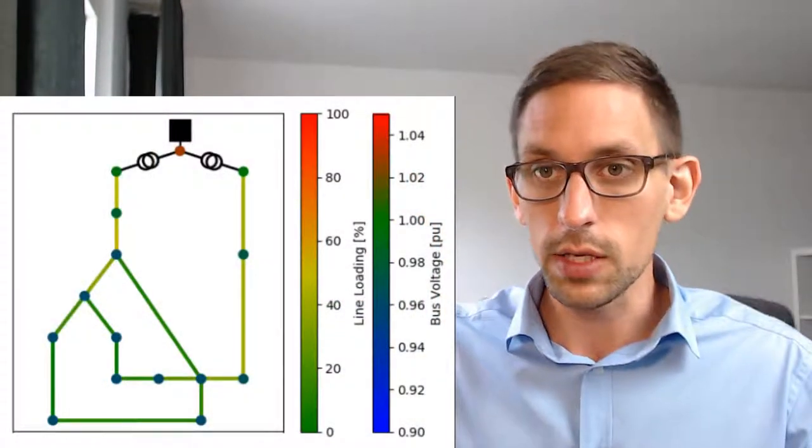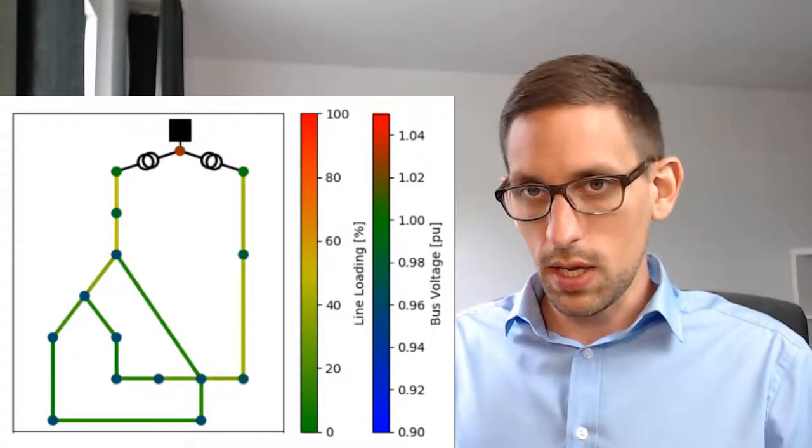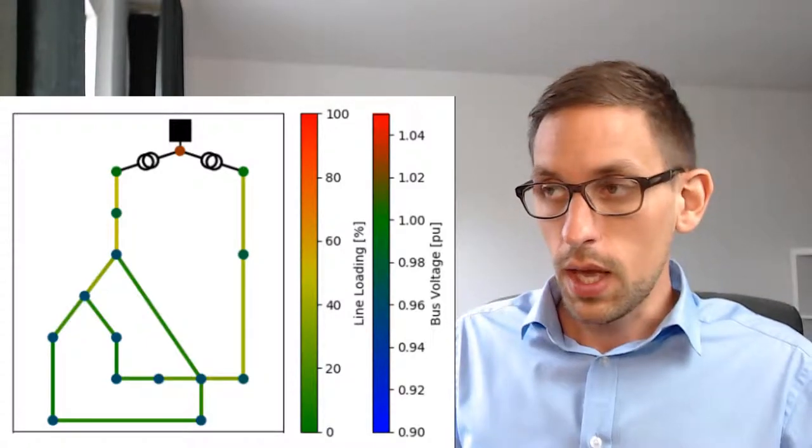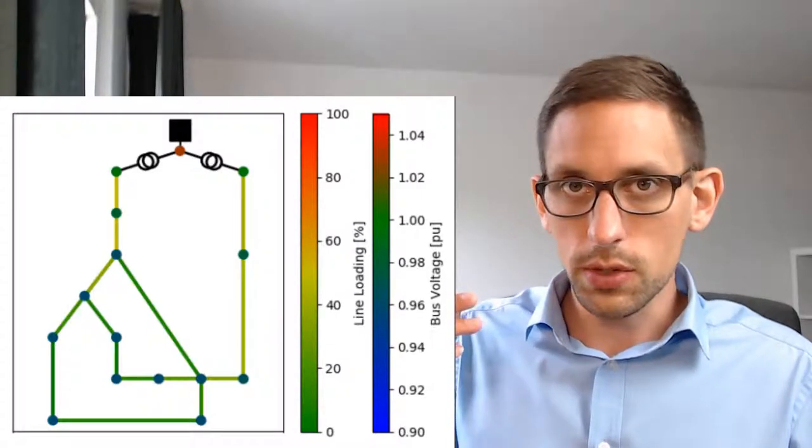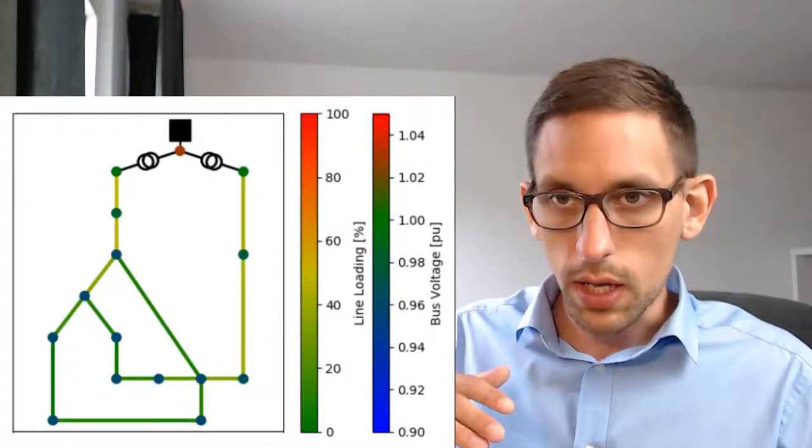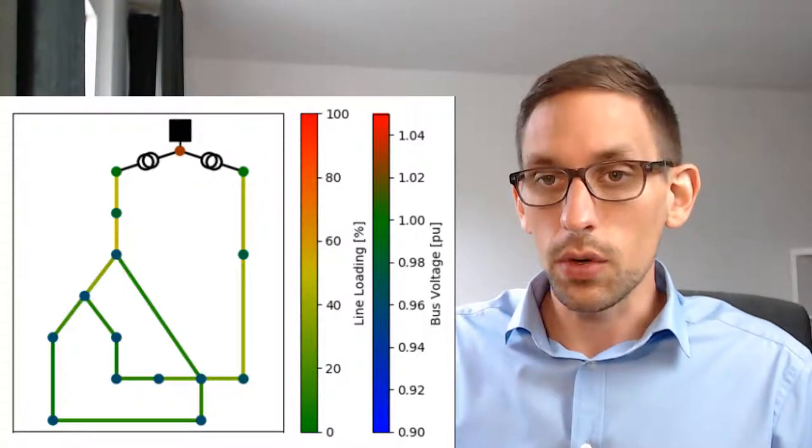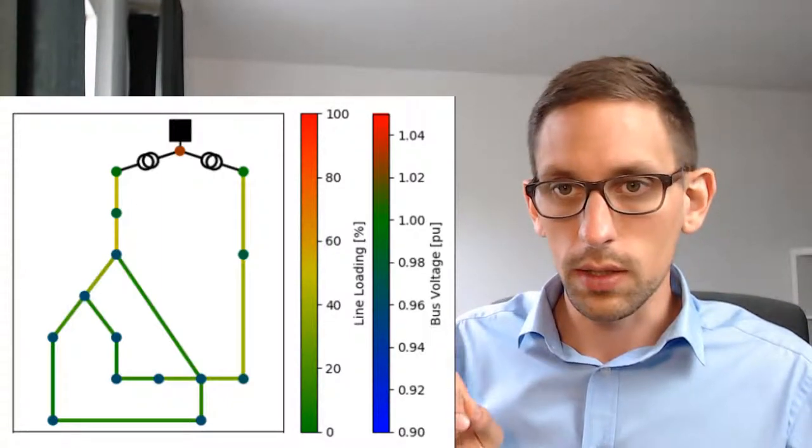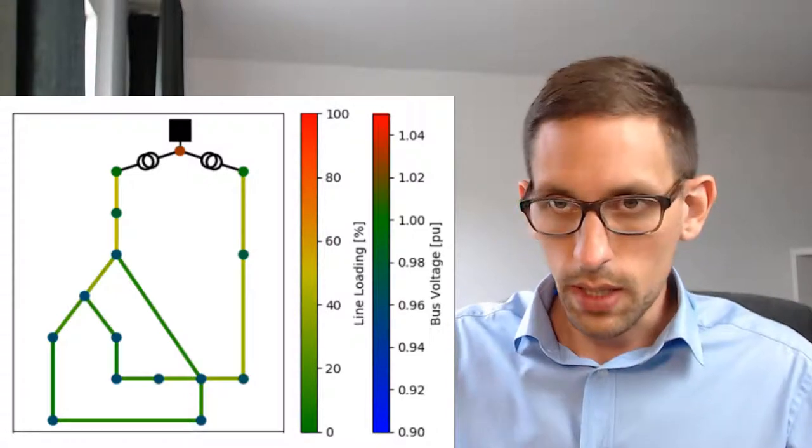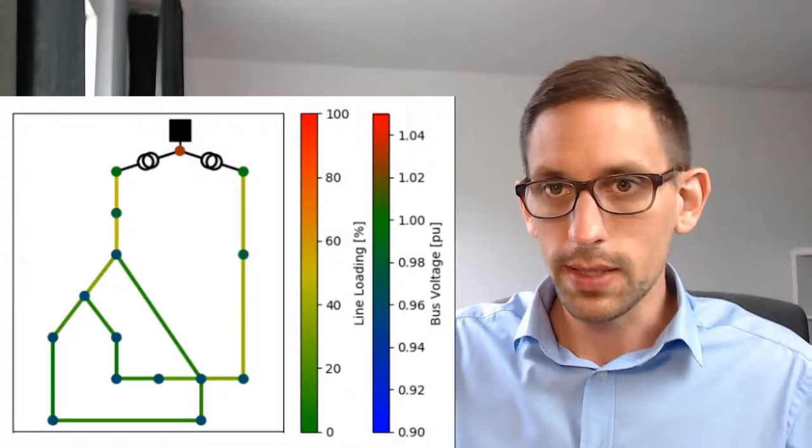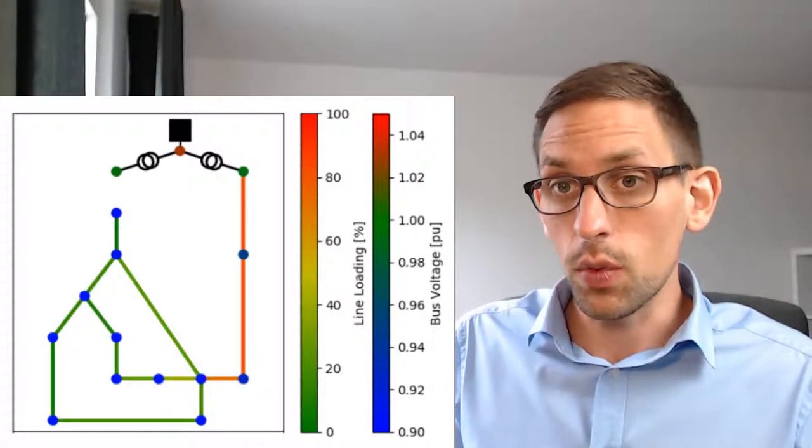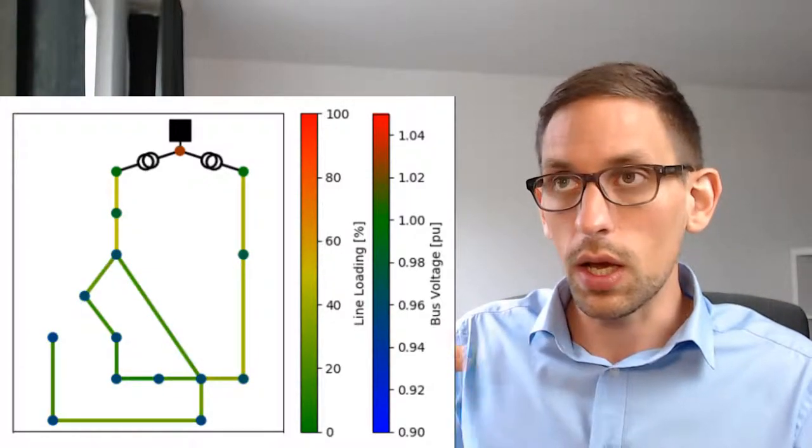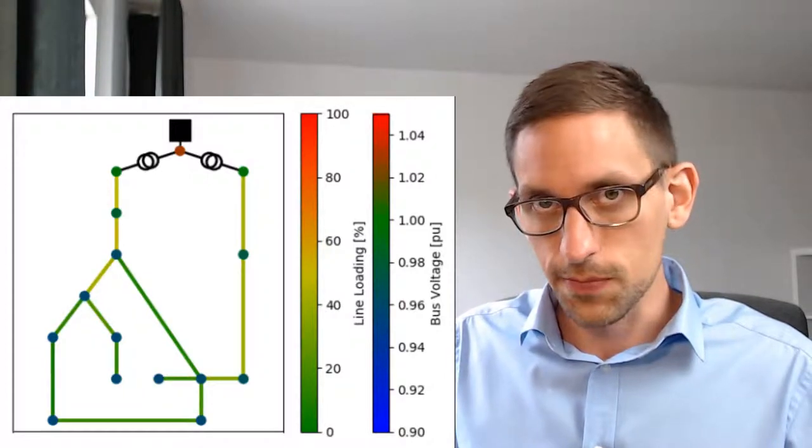An n-1 calculation means that if you have a grid like this one here and an asset fails, for example a line is outage because of trees falling on the line or whatever, then there might be some line loading or voltage problem in this grid. This can be analyzed, of course, by taking out each line after another and then checking what happens to the voltage or the line loadings at the other lines.